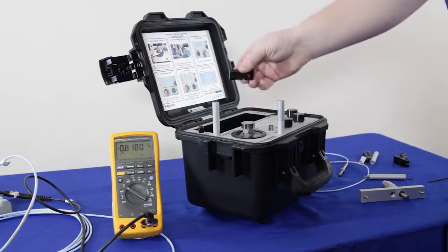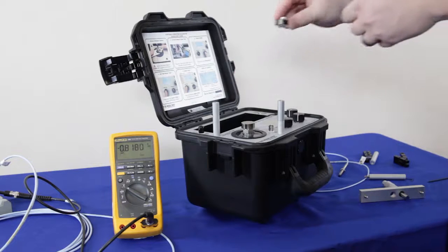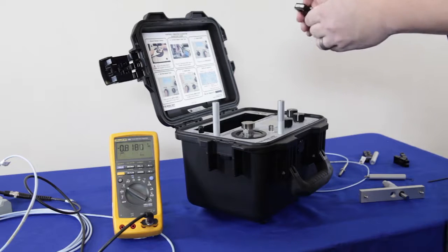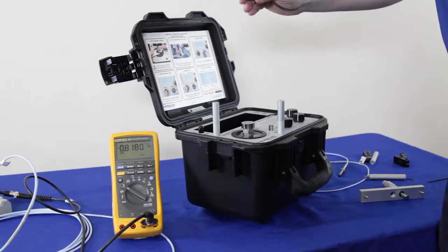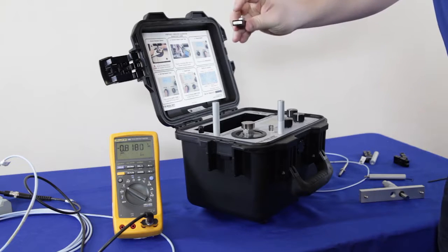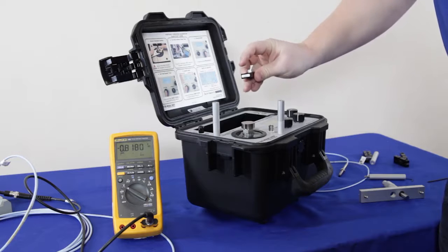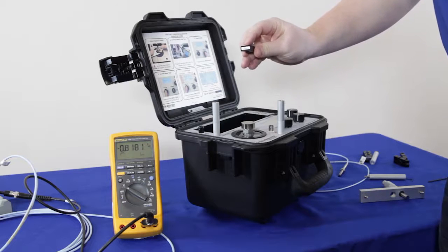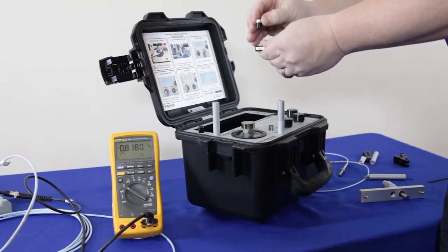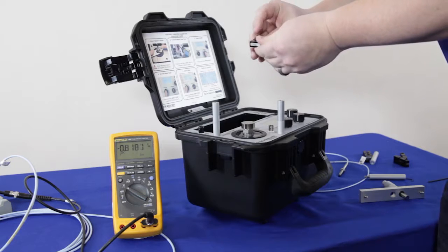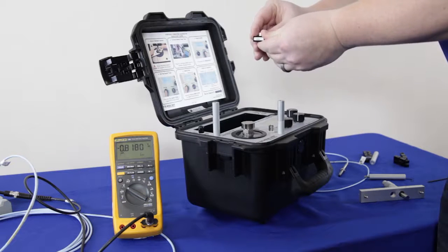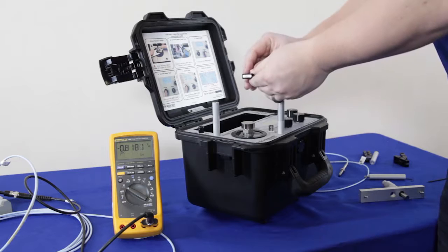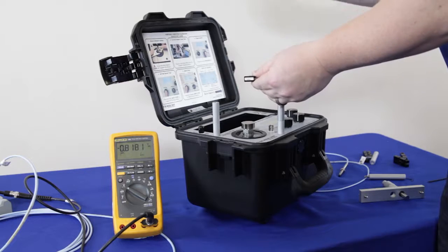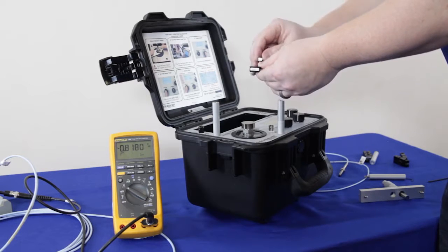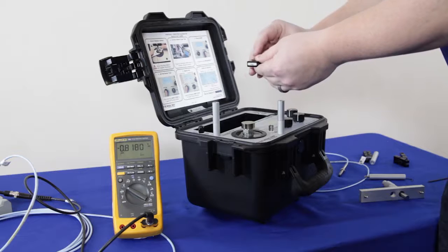The next step is to choose the correct mounting bracket. My proximity probe is 1/4 inch in diameter on the case thread, so I want to grab the 3/8 inch black mounting bracket with the 1/4 inch spacer that goes inside of it. So this is actually a little bit more complex. If you had just a 3/8 inch probe, then you wouldn't need the spacer, so it's an extra piece for this particular application, but it's relatively easy.